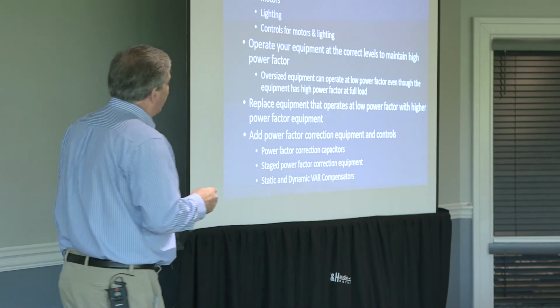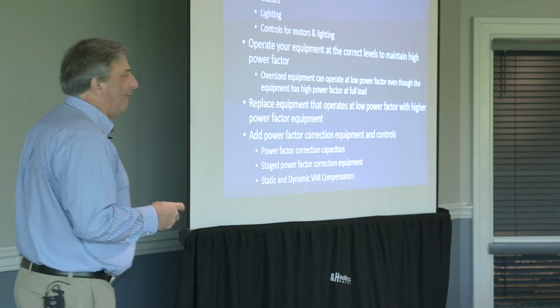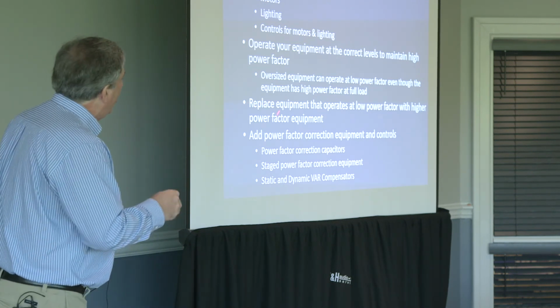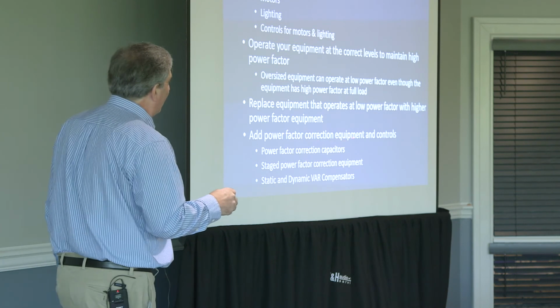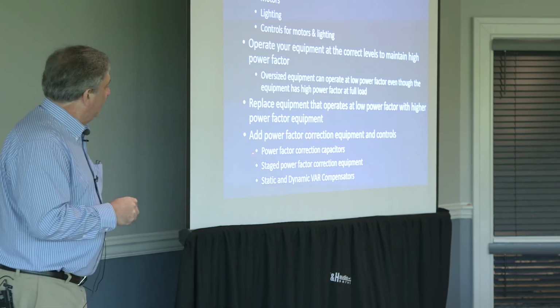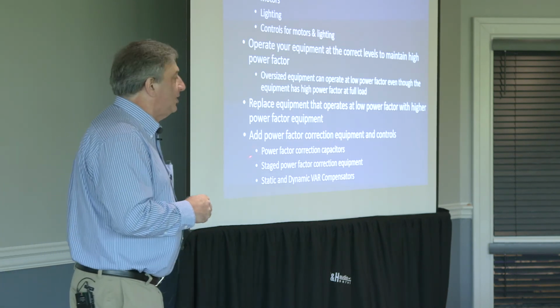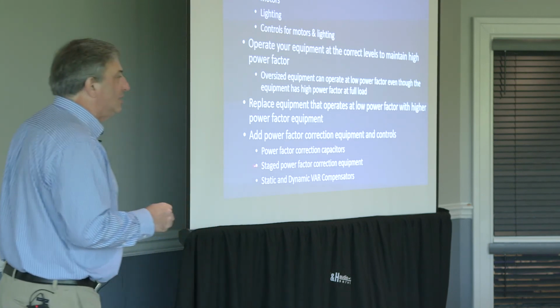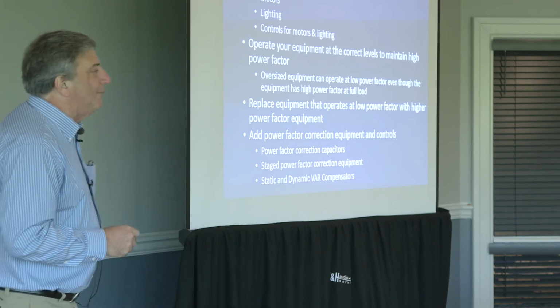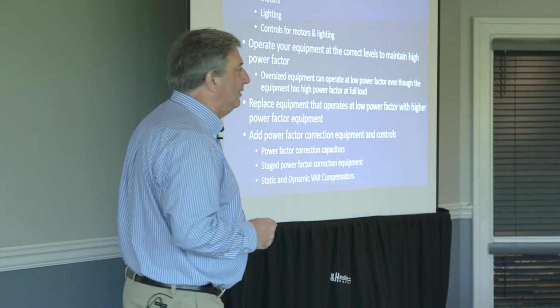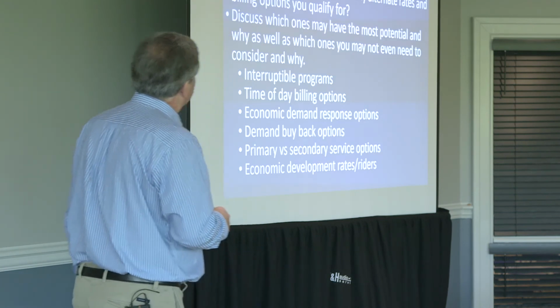Replace equipment that operates at low power factor with higher power factor equipment, we mentioned that. Or add power factor correction equipment and controls. That's typically power factor correction capacitors, a staged power factor correction system, or static and dynamic VAR compensators, which we'll talk about in a little bit. So those are our options.